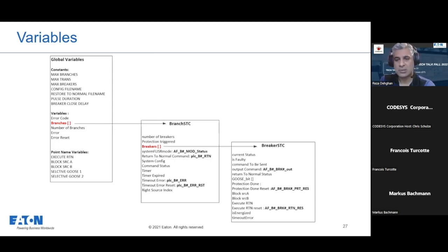And under breaker structure type, or breaker STC, I have all the information related to each of the breakers, stuff like what's the current status of the breaker, if it's faulty or not, what kind of command, or we were talking about that logical command that we send to the breakers before we actually send the physical commands, and of course some of the points that are coming from the relay. Those are the points that we have to send a command on, or we read some information from, and those are the physical points coming from the relay, unlike some of the logical points that we just create inside the CODESYS logic.